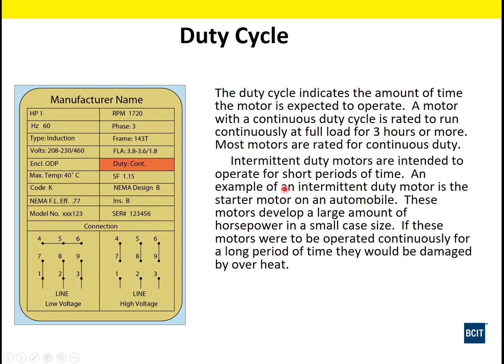Duty. Now, this is the frequency with which the motor is going to be operating. This one says continuous, so it can run continuously 24/7. Some of the motors are going to be sized with larger conductors if they have starting and stopping duty, where they start and stop frequently in a short period of time. When we do that to a motor, we're subjecting it to a lot of inrush current in a short time frame. So we have to be able to accommodate that with our conductors. If it's rated for intermittent duty or sporadic duty, we have to make sure we size our conductors to that. So when we're sizing our conductors, we have to take this duty into account.